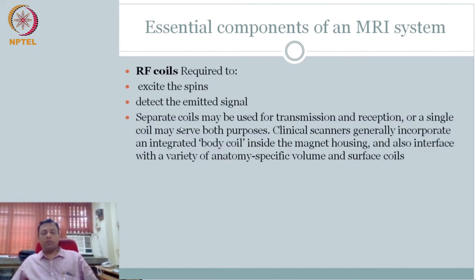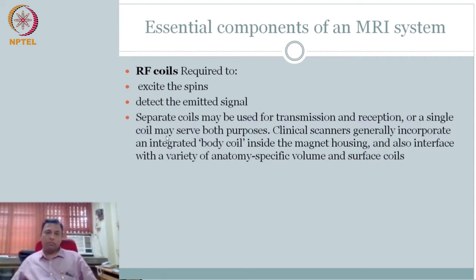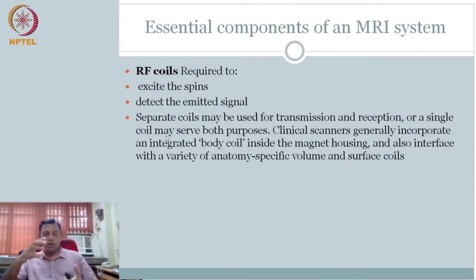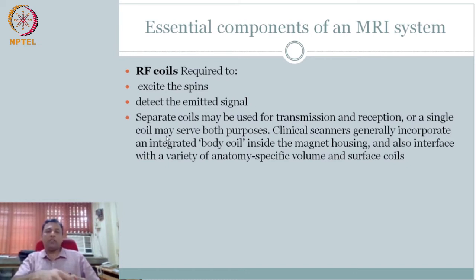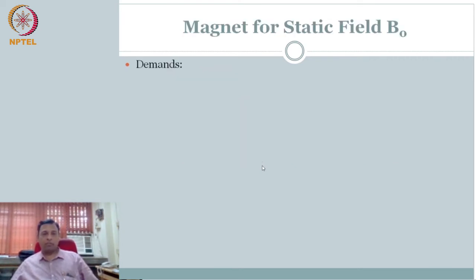The next component is the RF coil. You need the RF coil to both excite and then detect the transverse component. There are several ways to do it — you could have a transmit coil and receive coil separately, but typically it is a hybrid. Most systems have a body coil built in, but on top of that, for higher signal-to-noise ratio, they also use anatomy-specific coils. If you go for a scan of your elbow, you can have a coil specifically there. They might also put a surface coil on the knee to understand it better. Generally there is a body coil that comes built in with the scanner system.